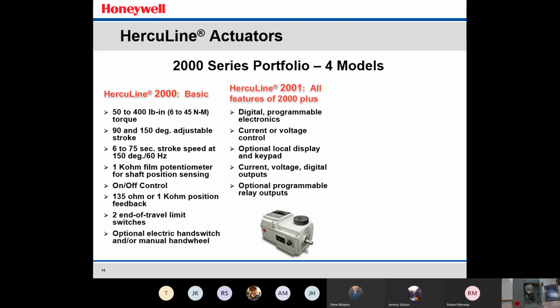The next model is the 2001 series. This one has some enhanced digital electronic features. So it does have programmable electronics. On this actuator here, you can either use a display or there is a port that you can connect up to and program the actuator that way through an RS-485 Modbus communication link. You can either do current or voltage control on this particular model, optional local keypad, and it accepts current, voltage, or digital outputs.